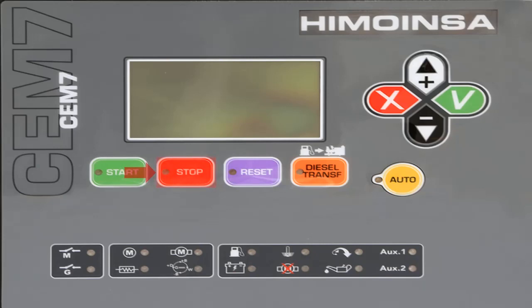Pressing the stop button initiates the engine stopping procedure with a cooling time of 120 seconds. If the button is pressed two times, it causes the engine to stop immediately without waiting for the cooling time, or generating an emergency stop alarm.